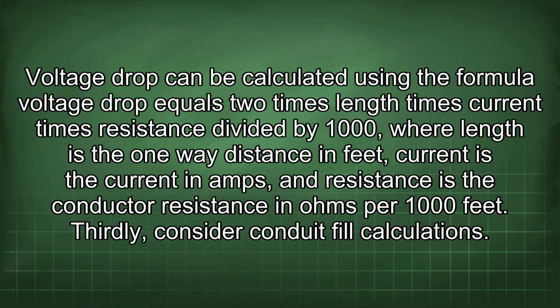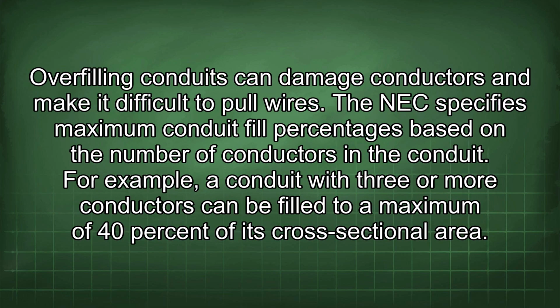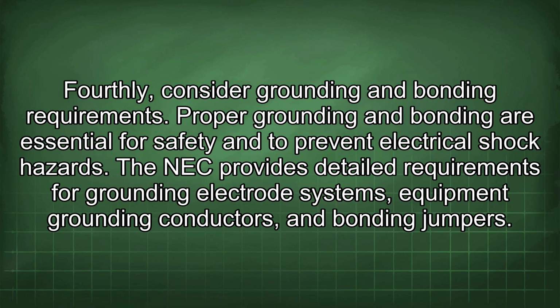Thirdly, consider conduit fill calculations. Overfilling conduits can damage conductors and make it difficult to pull wires. The NEC specifies maximum conduit fill percentages based on the number of conductors in the conduit. For example, a conduit with 3 or more conductors can be filled to a maximum of 40% of its cross-sectional area. Fourthly, consider grounding and bonding requirements.